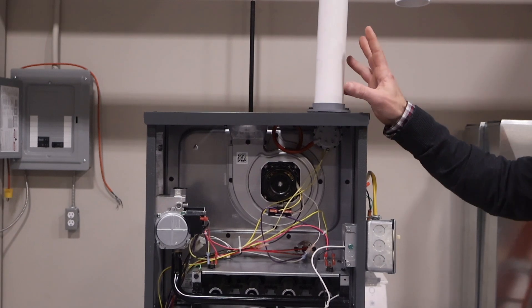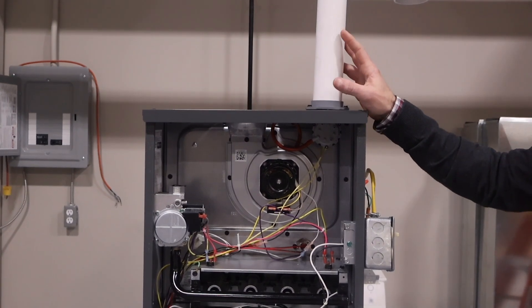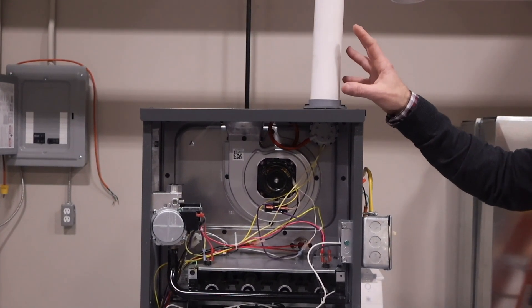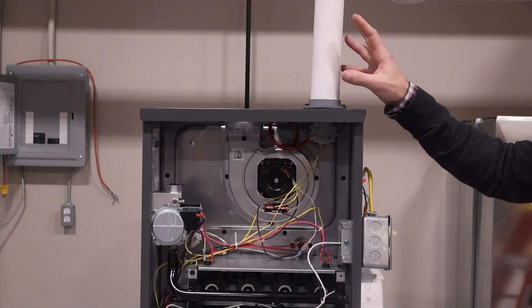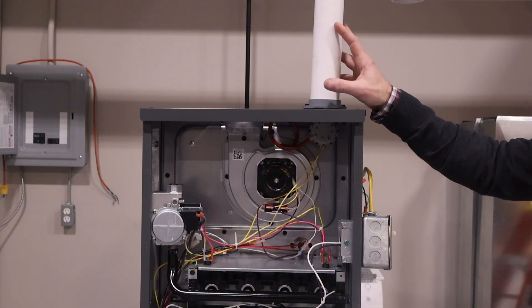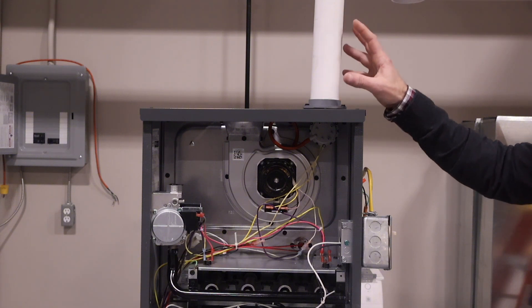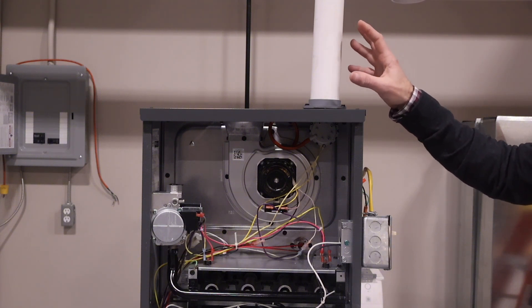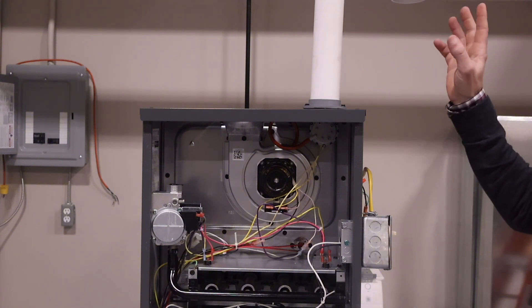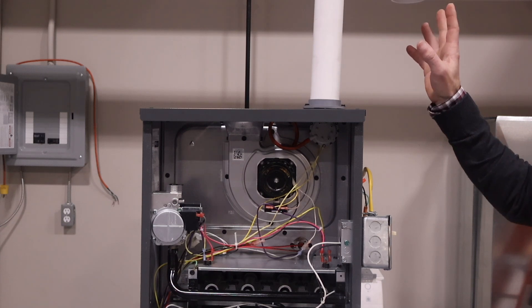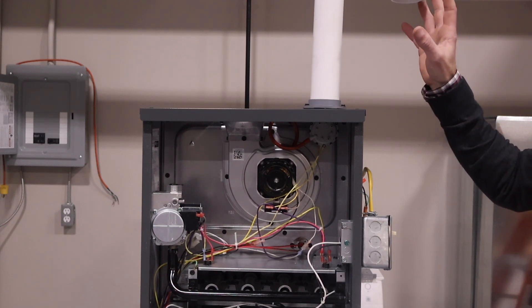The combustion air intake pipe kit is required on all 80% furnaces paired with refrigeration unit using an A2L refrigerant. This kit will prevent any A2L refrigerant from entering the furnace through the combustion air intake in case of any leaks.